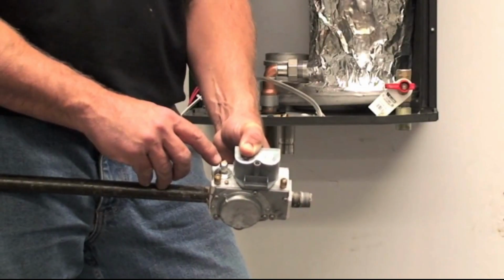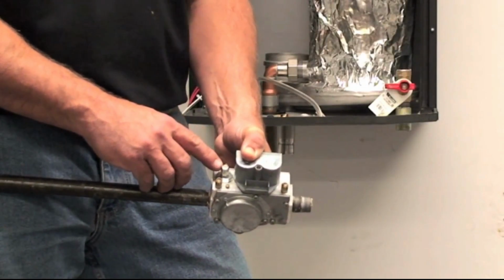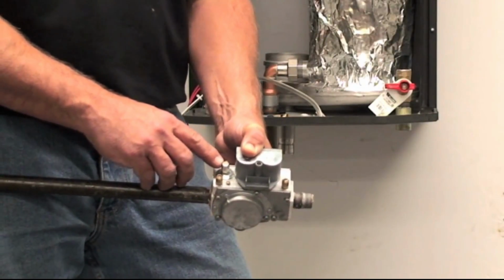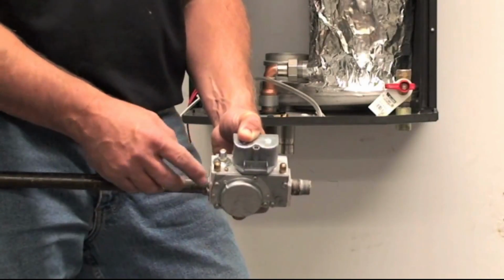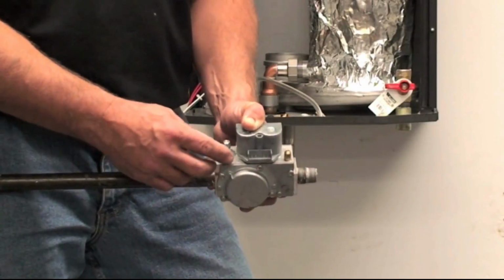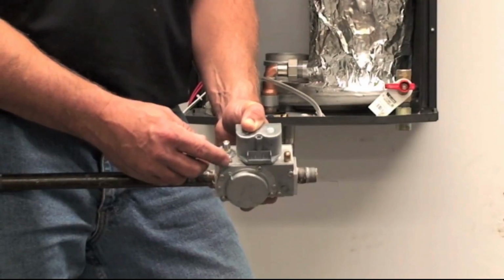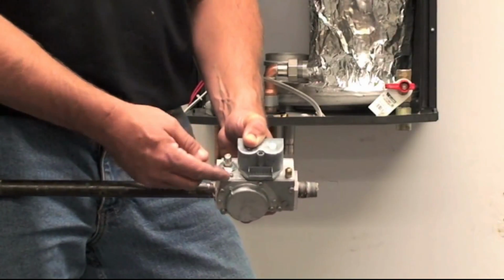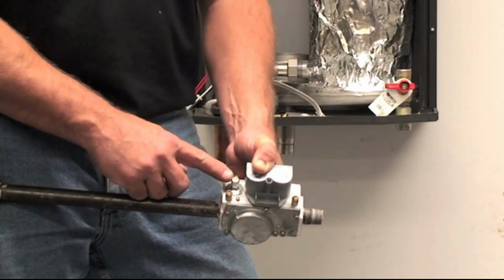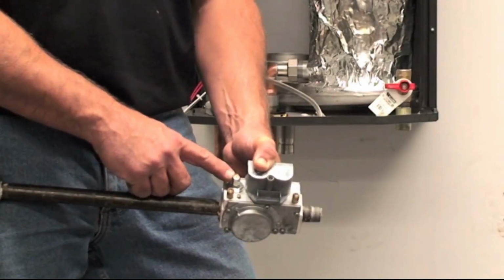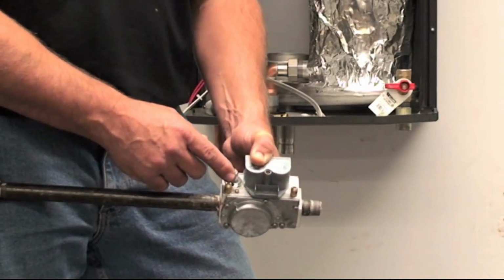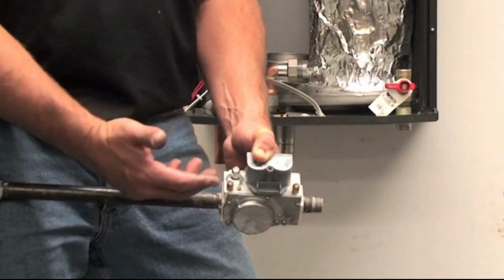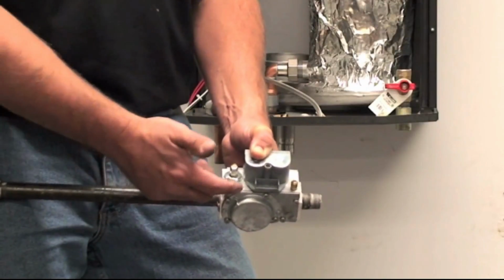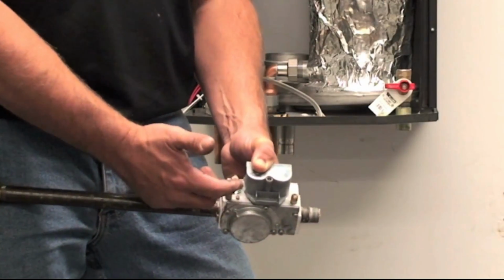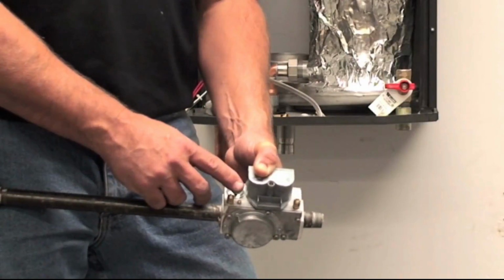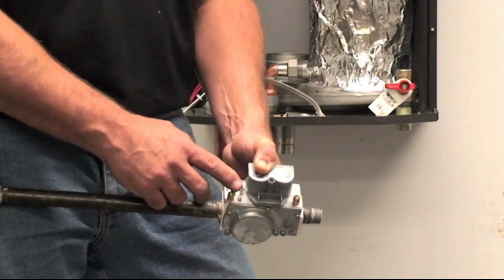And that normally is, if you ever have to adjust that, that's mainly for light off. The rule of thumb is if this throttle is adjusted where you want to increase fuel, there's a plus. We're going to go to the plus side. Well, if you're doing your offset, it is exactly opposite. So in other words, if you forget which direction you need to go, your throttle, you're going to turn one way. Your offset is going to be the exact opposite to provide the same function.